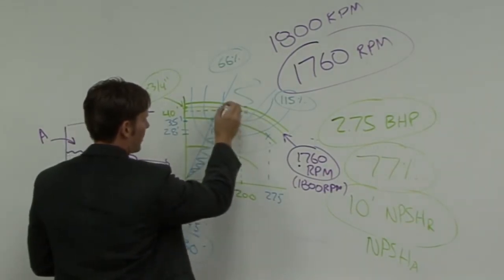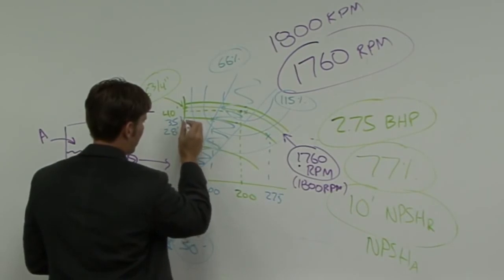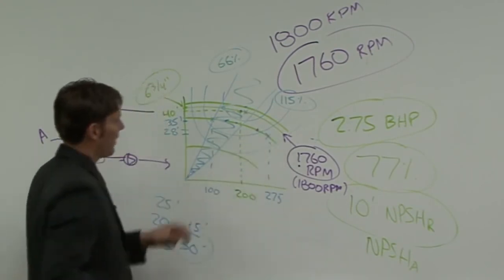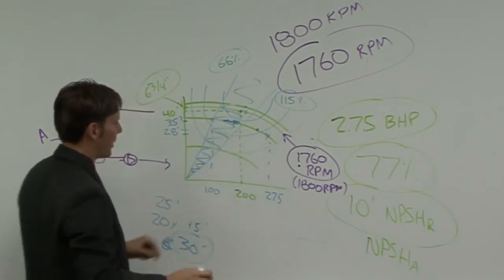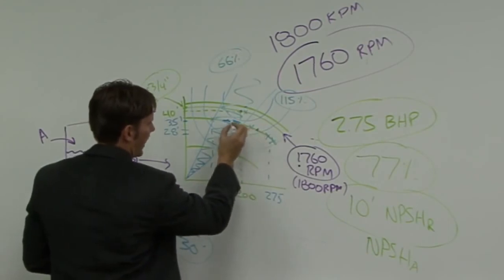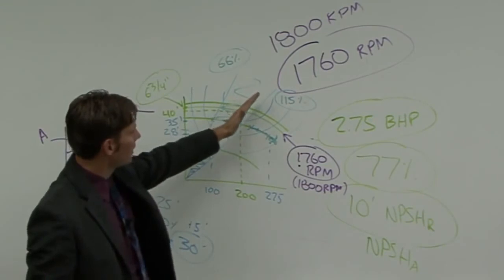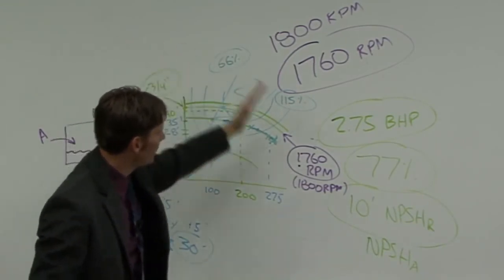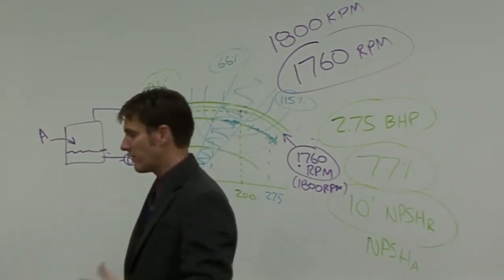And what's that going to do on the pump curve? Instead of operating here, they could operate out over here. So what it does is it could pull them closer to best efficiency point. But if they selected the pump out over here and then they lost their head pressure, it takes them further away from their best efficiency point. So that's why ASHRAE gives us more leniency to the left, because with the safety factors that are being used, it will pull us back, in reality, towards a higher efficiency point, not further away from it.